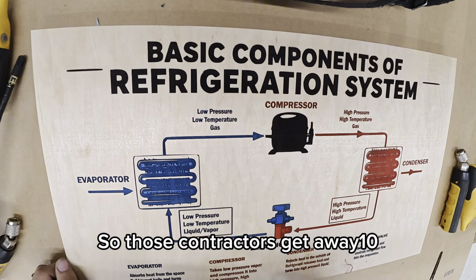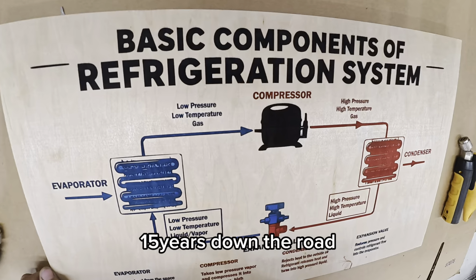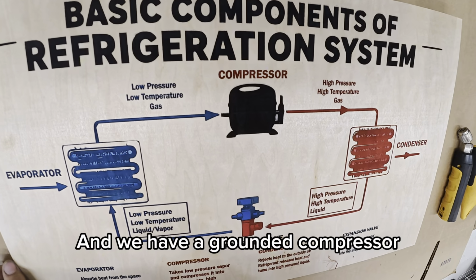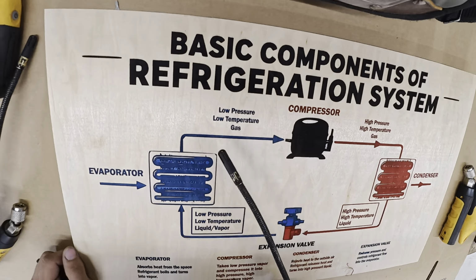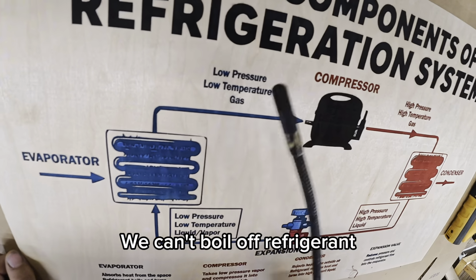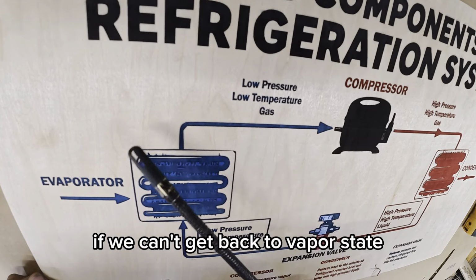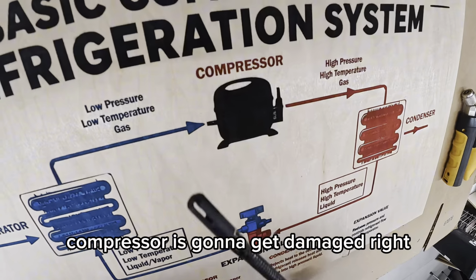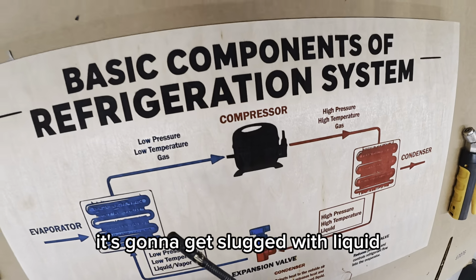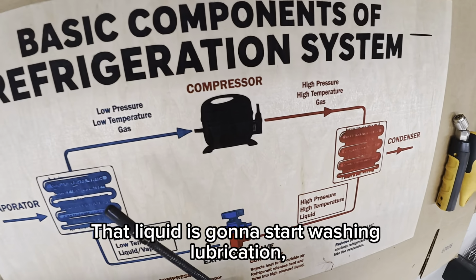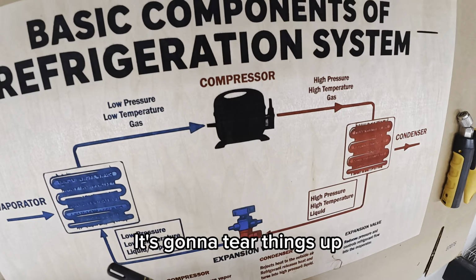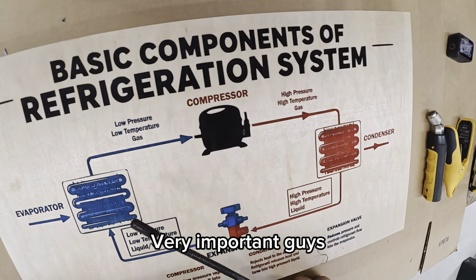So those contractors get away with it 10, 15 years down the road, and we have a grounded compressor, and we wonder why, right? If we don't have the airflow, we can't boil off refrigerant. If we can't get back to vapor state, the compressor is gonna get damaged, right? It's gonna get slugged with liquid. That liquid's gonna start washing away lubrication. It's gonna tear things up. So very, very important, guys.